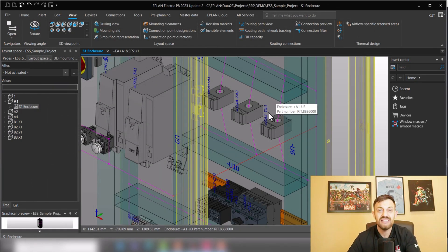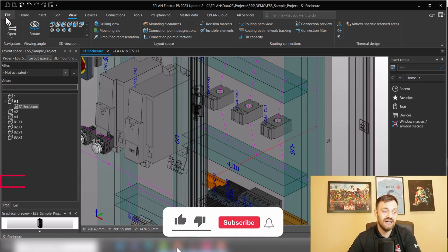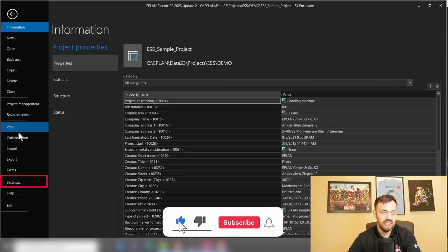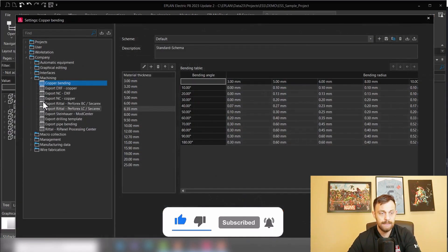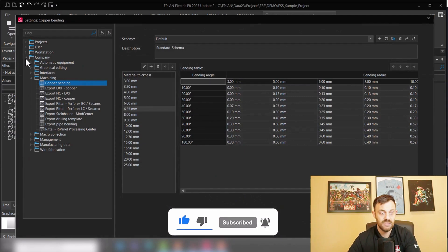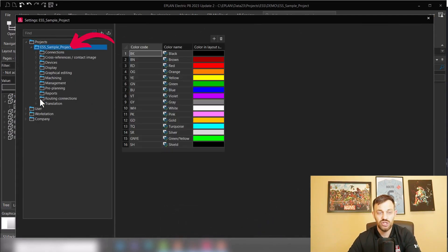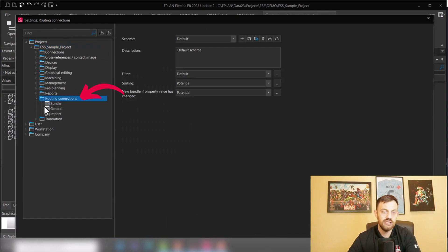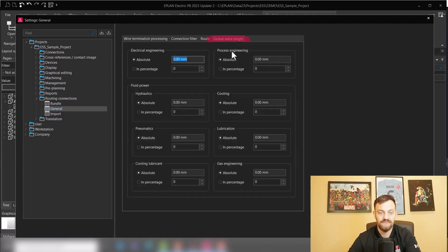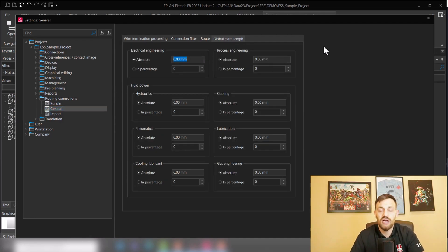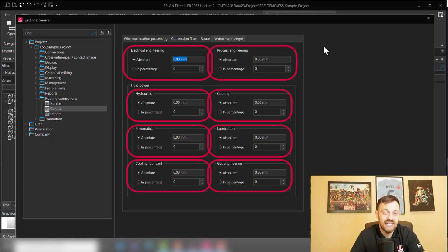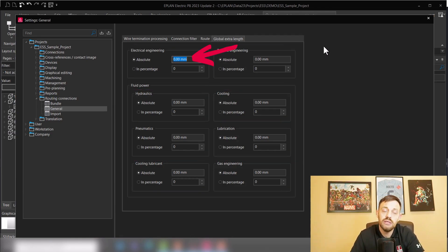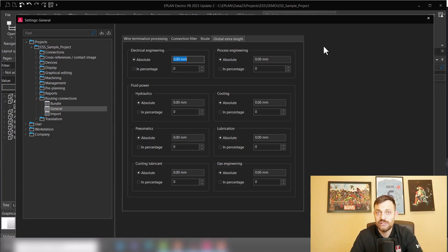And now the third way, and probably the most used way, is the global extra length. You can find this under File > Settings > Projects > Project Name > Routing Connection > General. And here is a tab called Global Extra Length, and here you have the possibility for every function group to add an extra length either as absolute or in percentage addition.